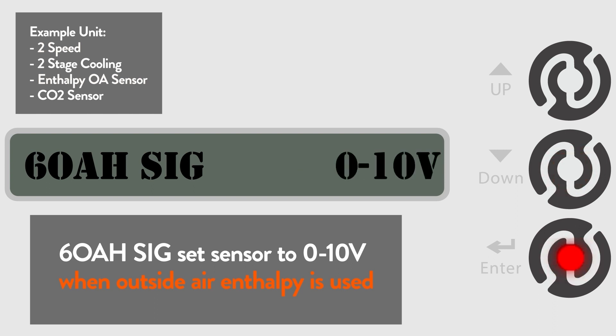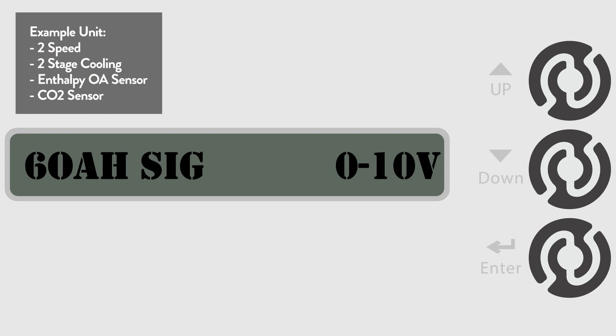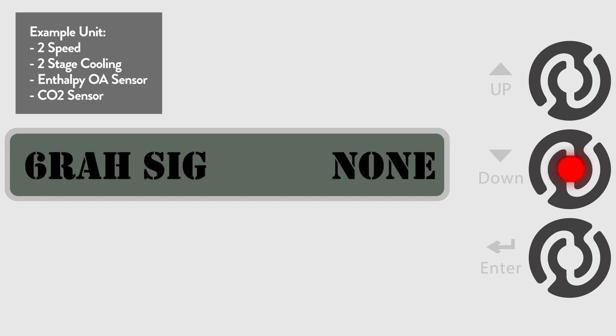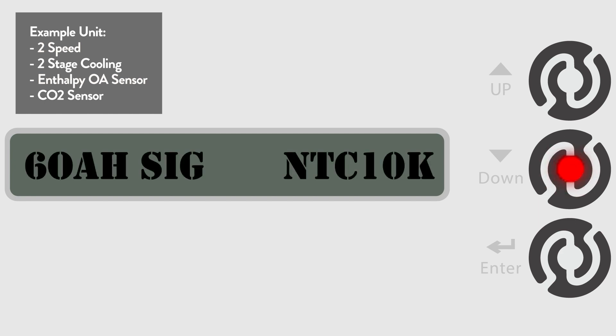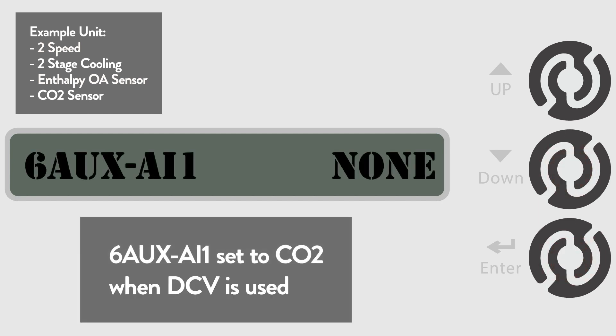Once we get to the run state section, we will set up the humidity setpoint. The default setting for CO2 is none, meaning the controller assumes that a CO2 sensor is not being used. Go to the 6 AUX AI1 menu and change the default setting from none to CO2. This tells the controller that a CO2 sensor is now being used.